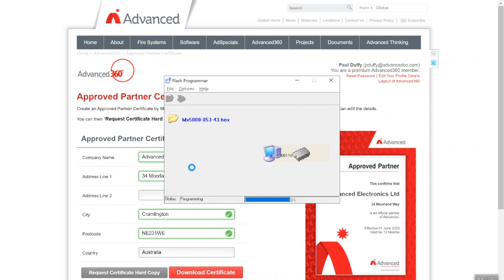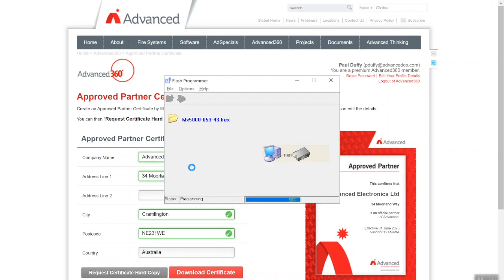The panel will start to buzz - obviously if it's on a network it will generate a network fault as we're going through this process. Remember it's putting the panel back to factory default and updating the operating firmware, so it will display a no communications logo. The buzzer will start to operate but that's a normal operation. You can mute the buzzer if it goes off. Currently at 63 percent.